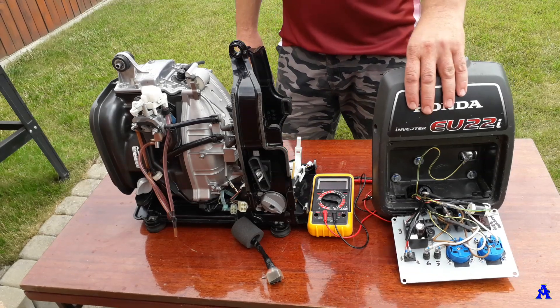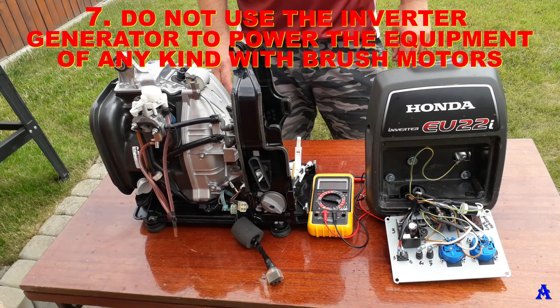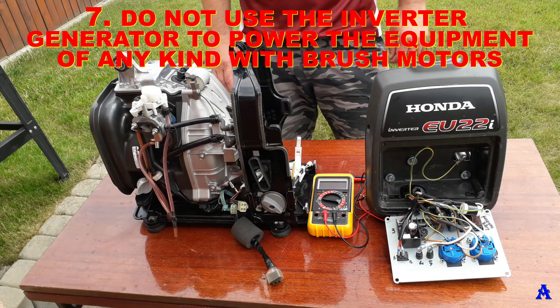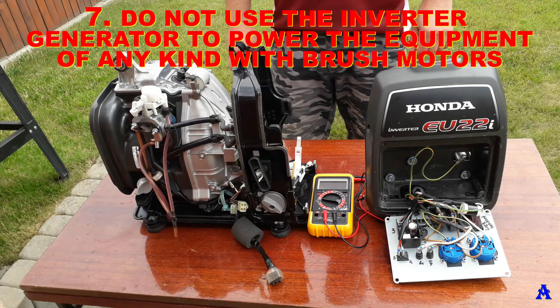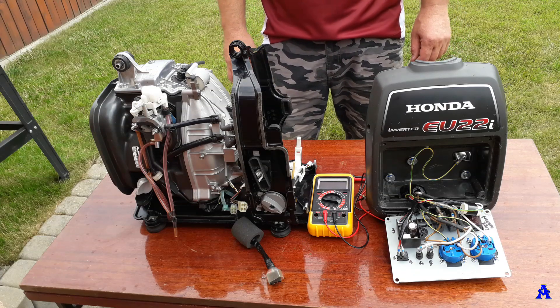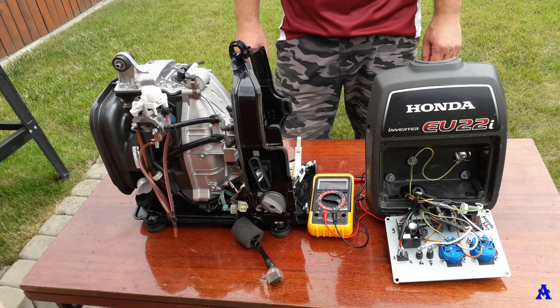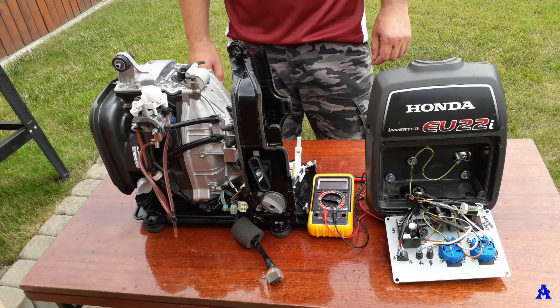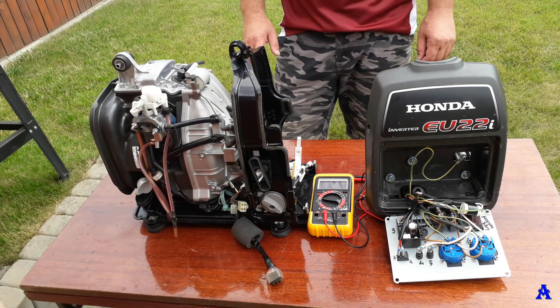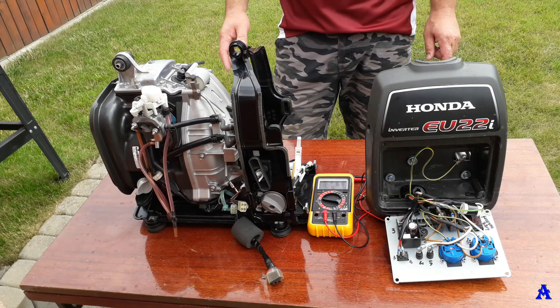Sin seven: do not use inverter generators to power equipment of any kind with brush motors. Why? Because these brush motors, when the brushes are worn, can send power surges back toward the generator that can damage the electronic card. To power this kind of tools and equipment, please use classic generators with a classic alternator with a stator and heavy rotor instead.